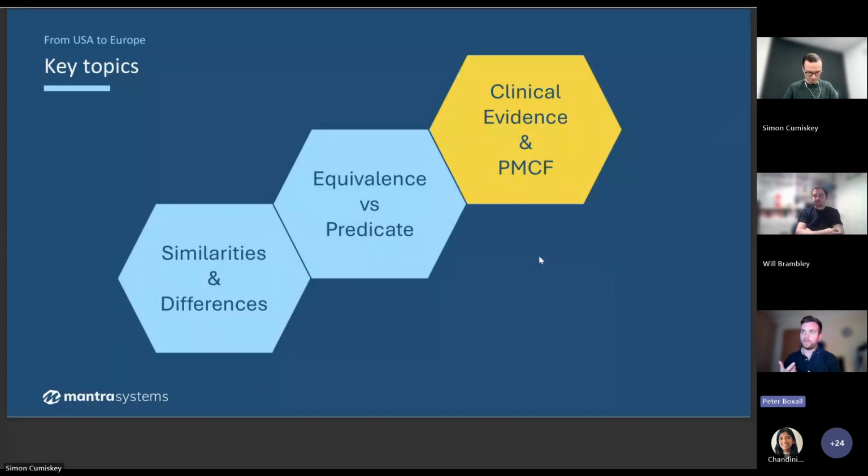We use that information to re-evaluate and reassess the severity and probability of risks that have previously been identified in your initial submission and your initial risk management activities. If we have said that pain associated with use of the device is negligible or very low likelihood, as we've collected data going forward through post-market clinical follow-up, is that true?